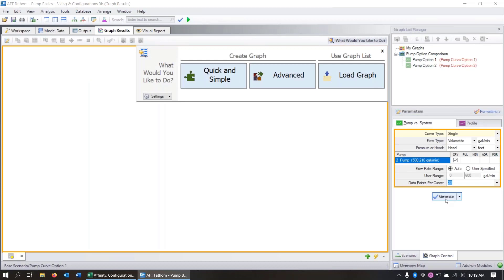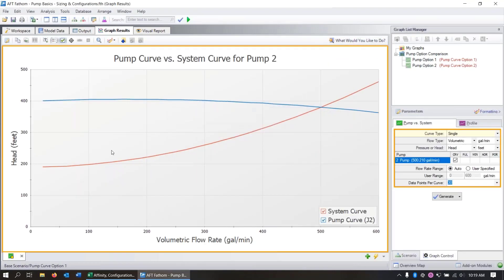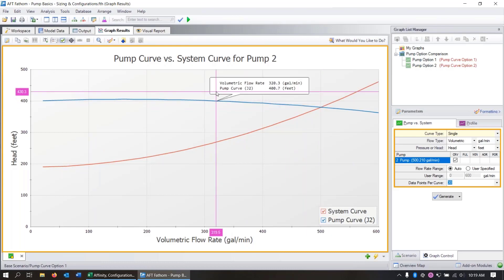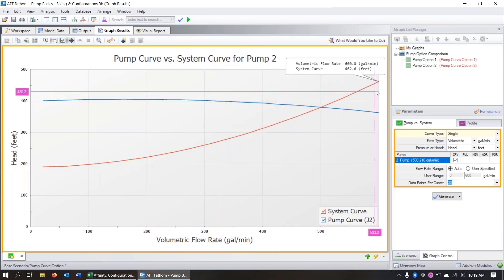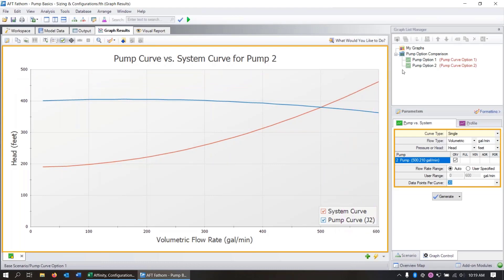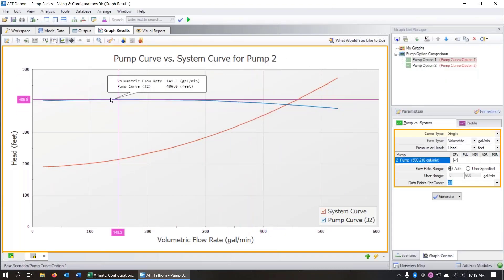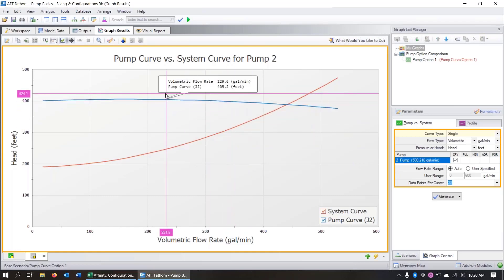If we go to graph results and generate the pump versus system curve, we see the same system curve with the pump curve overlaid on top. Showing the crosshair, we confirm the intersection at our operating point of 500 gallons per minute and 381 feet of head. We want to save this for future reference. To compare pumps across multiple scenarios, we can save this as pump option one for later comparison.